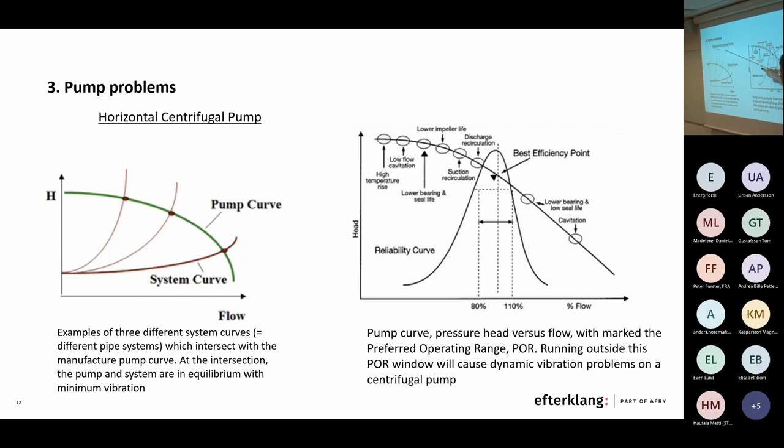And what's also affecting the horizontal centrifugal pump is the foundation and the connecting pipe system. And there is a pitfall which I brought up in my former Energiforsk project, vibration measurement pitfalls, which has to do with pumps. Otherwise, you think about the foundation, that is the tuning of your machine. But what happens if your connecting pipe system is stiffer than your foundation? It's like you have an upside down foundation.